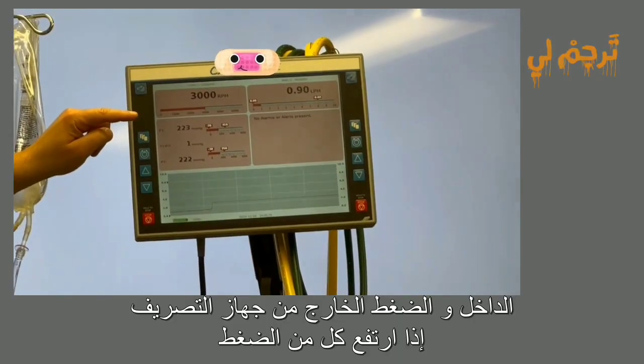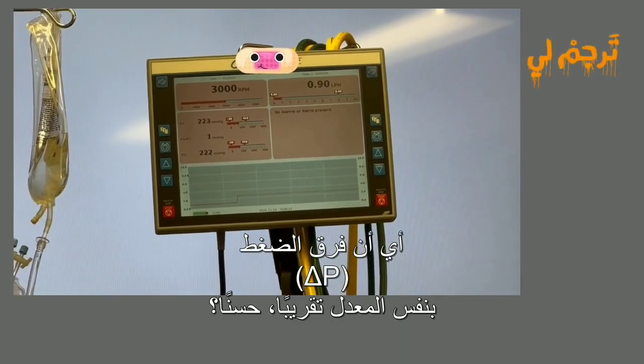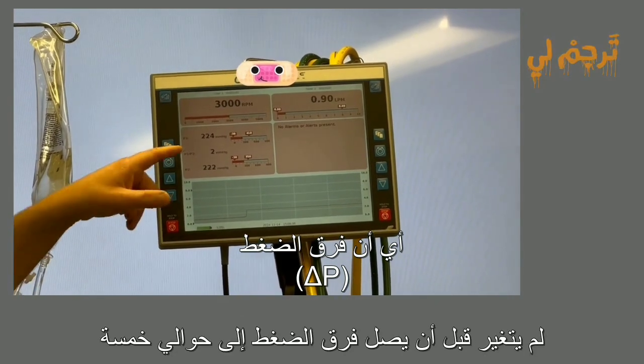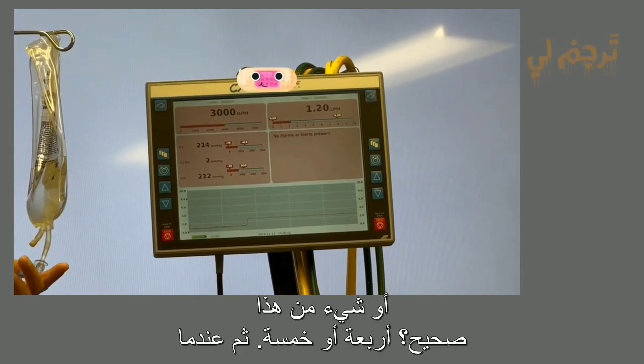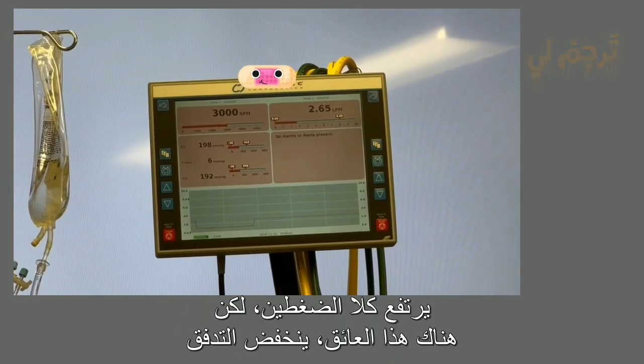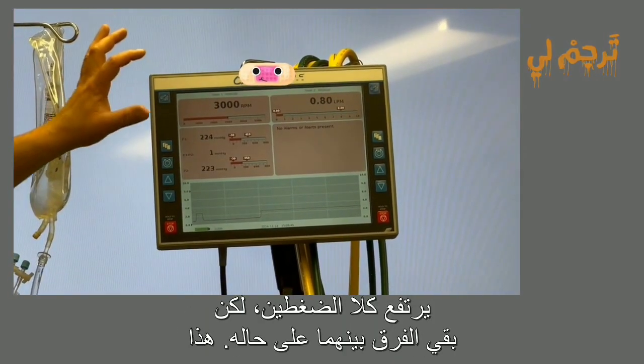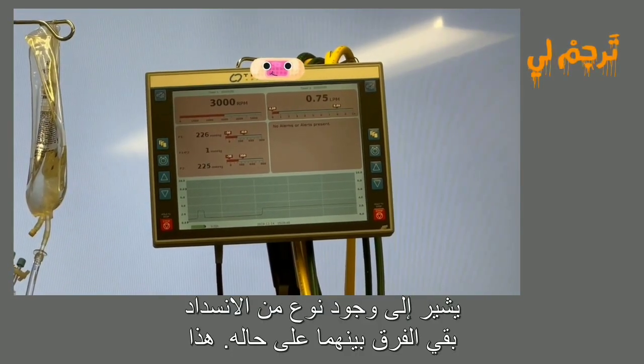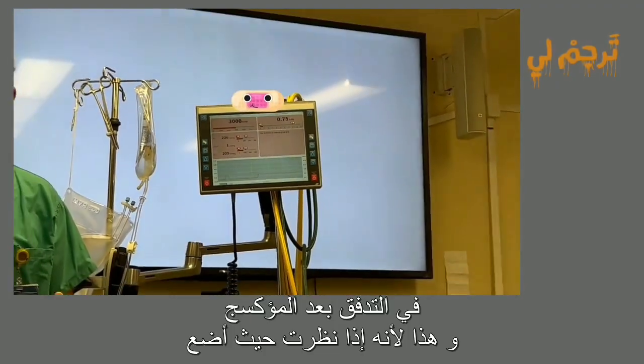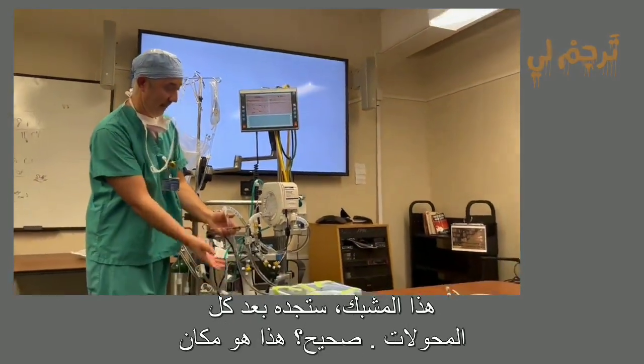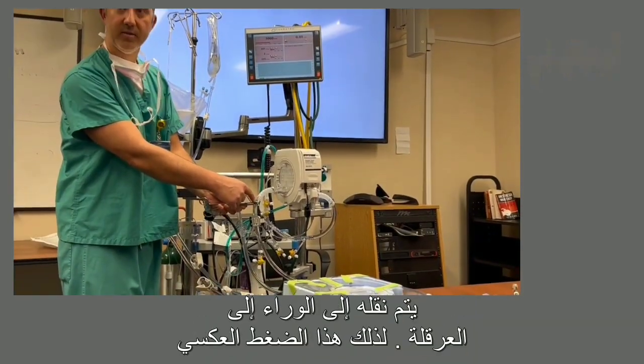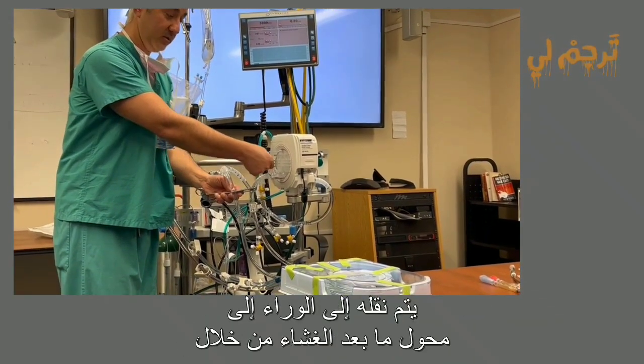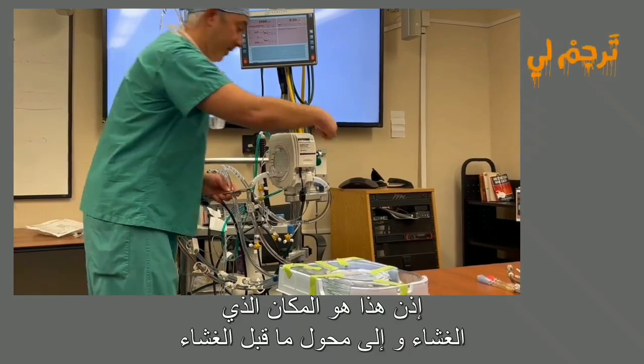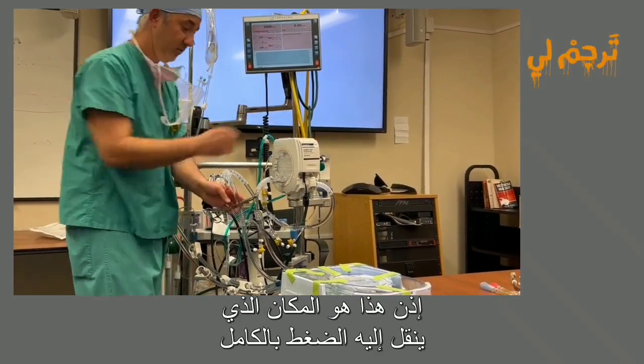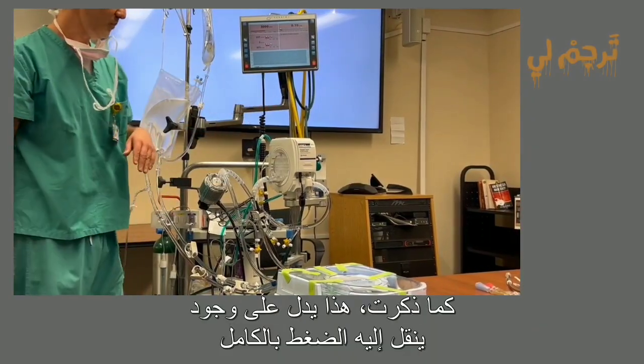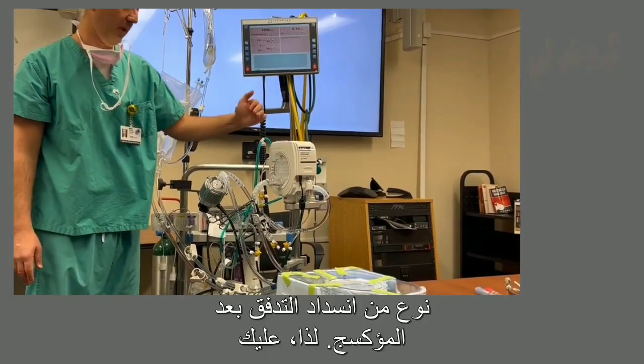If both the pressure going in and the pressure coming out of the oxygenator go up at about the same rate, meaning that your delta P didn't really change. Right before, the delta P was about 4 or 5, and then when there's that obstruction, the flow went down, both pressures went up, but the difference stayed the same. That's indicative of some sort of obstruction of flow beyond the oxygenator. And that's because if you look where I put this clamp, it's after all the transducers. This is where the obstruction is. So that back pressure gets transmitted backwards to the postmembrane transducer, through the membrane, and to the premembrane transducer. So like I said, that's indicative of some sort of obstruction of flow after the oxygenator.